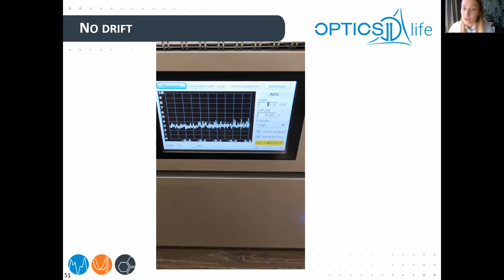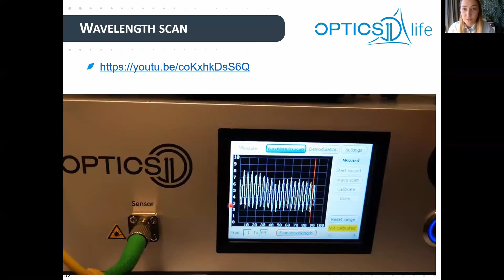Now, there's another trick regarding how to decrease the noise level, and that is by increasing the laser power. So for example, I did here the wavelength scan, and then I look in the details about the gain, offset, and range. And I see here that range is high. Of course, you see that the signal is not on the circle. That's because we didn't calibrate it yet. We only did the wavelength scan. The signal will be on the circle only when you do the calibration. So don't panic yet. That's coming.